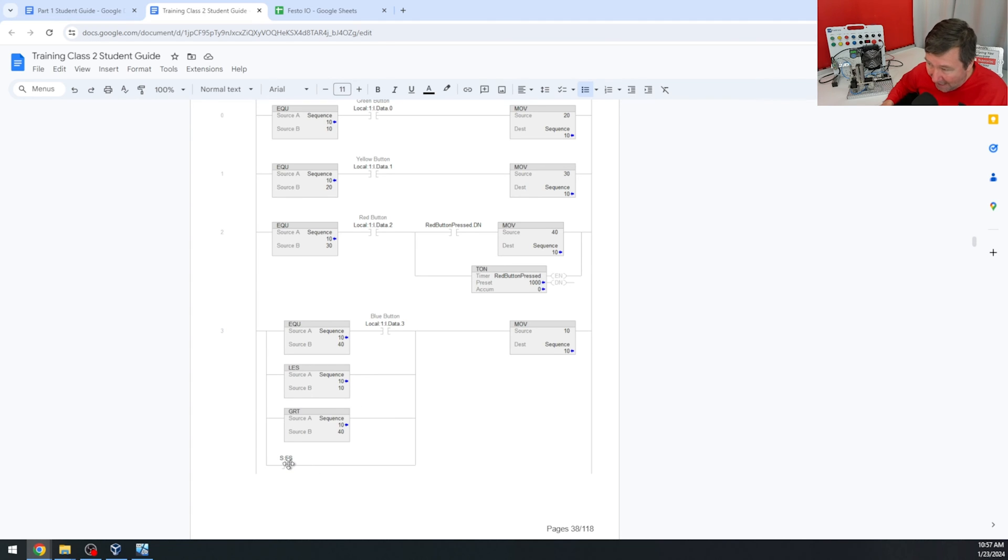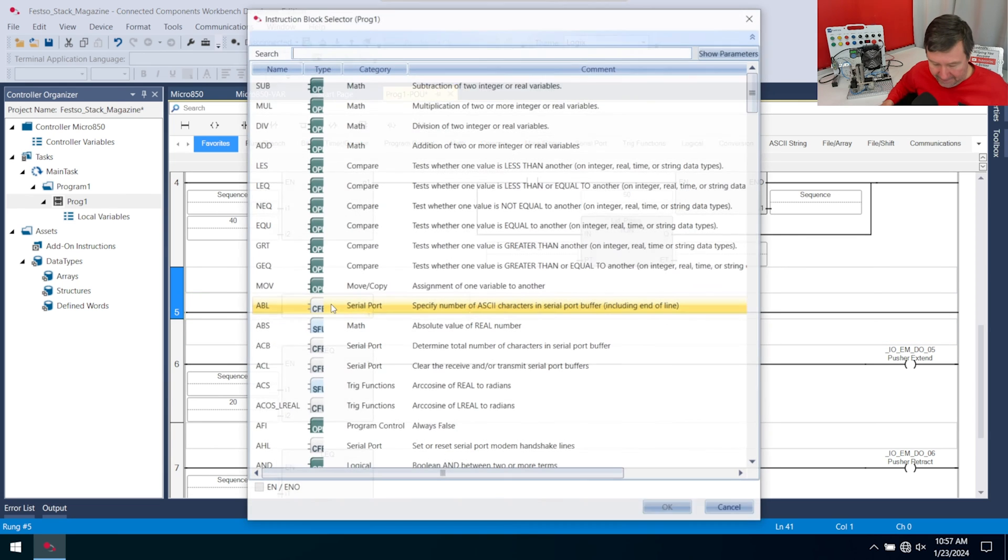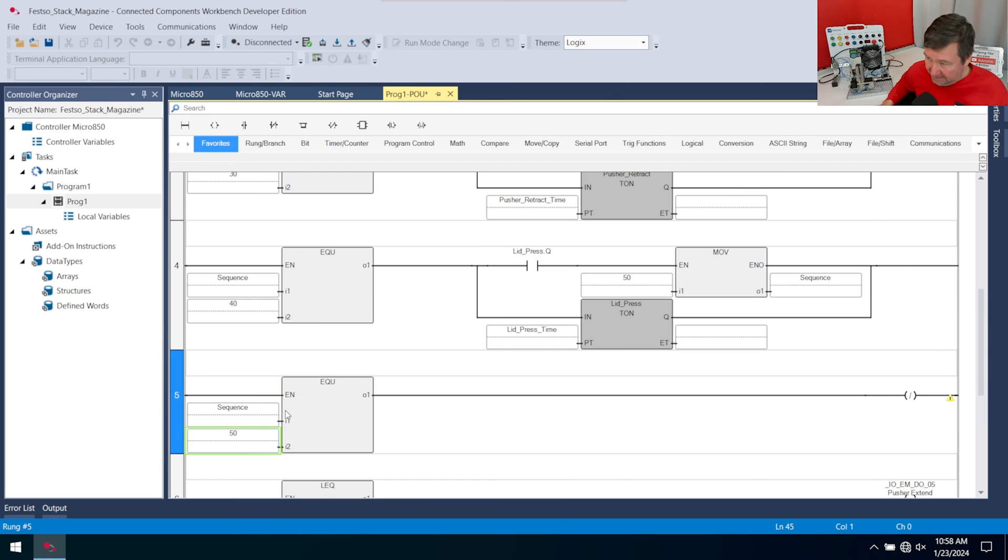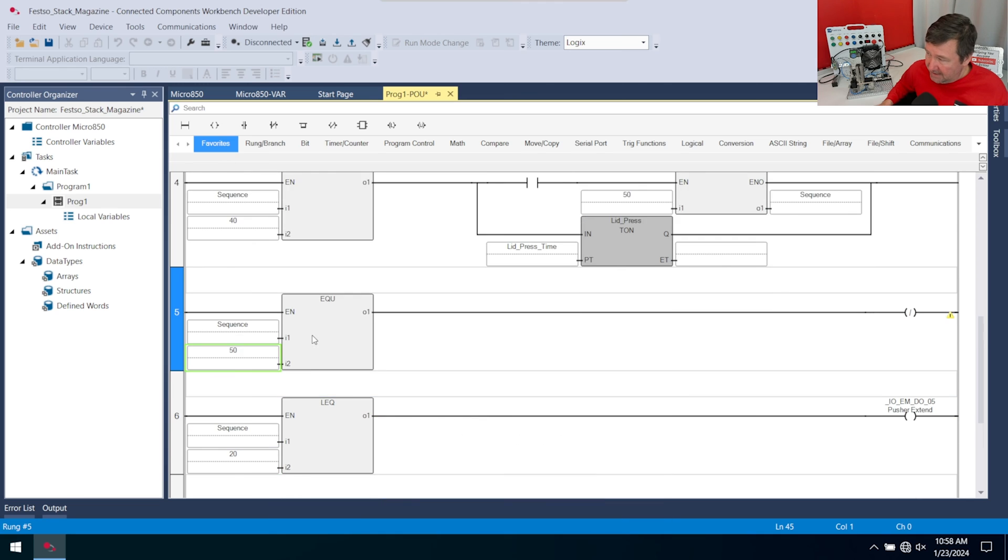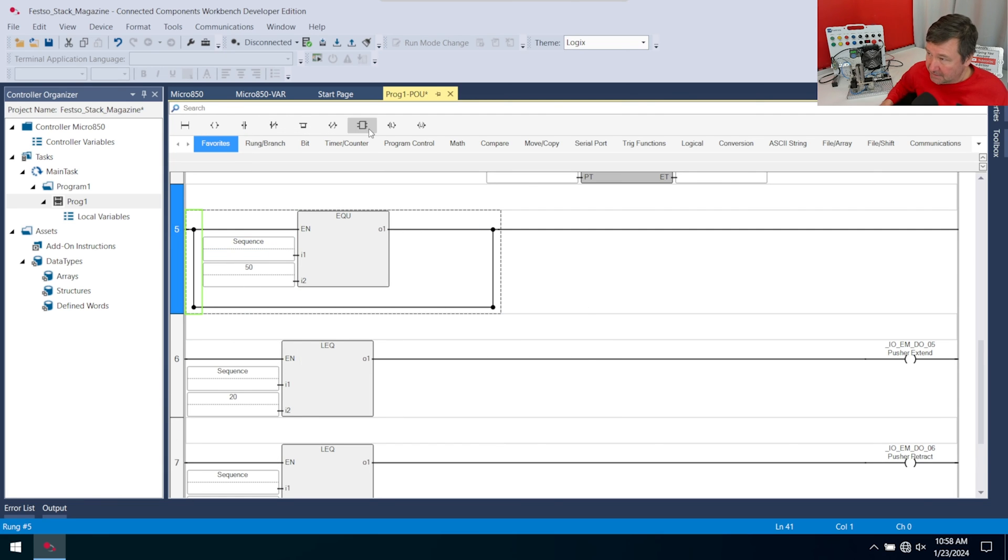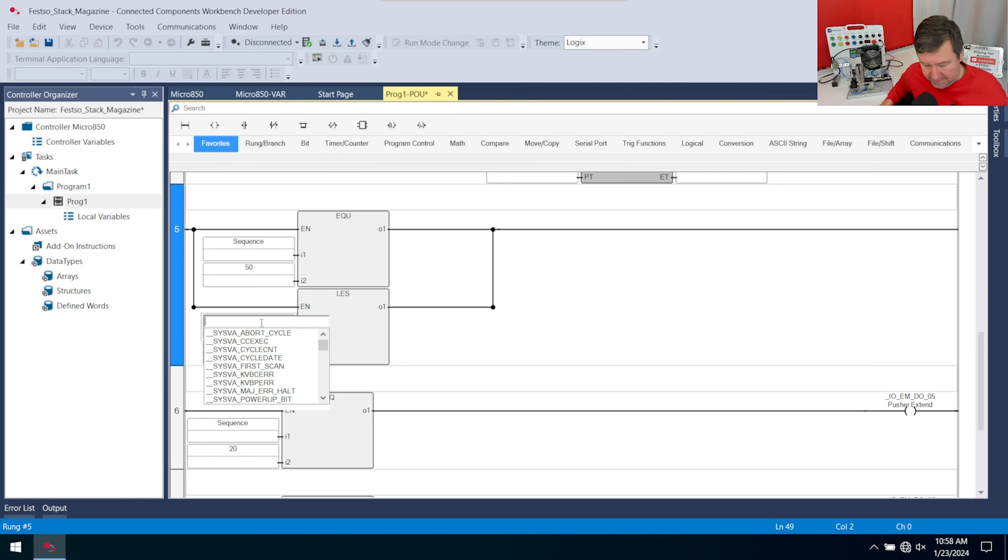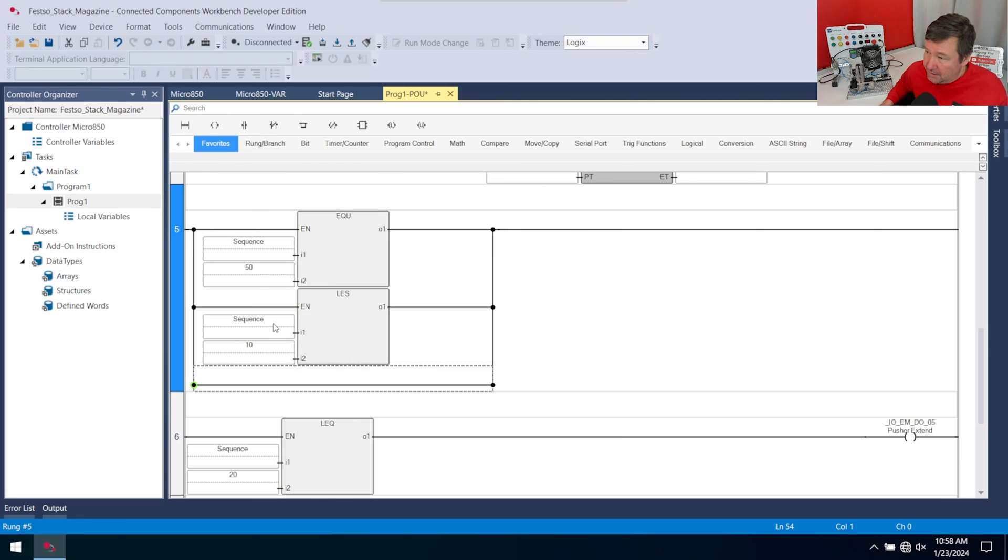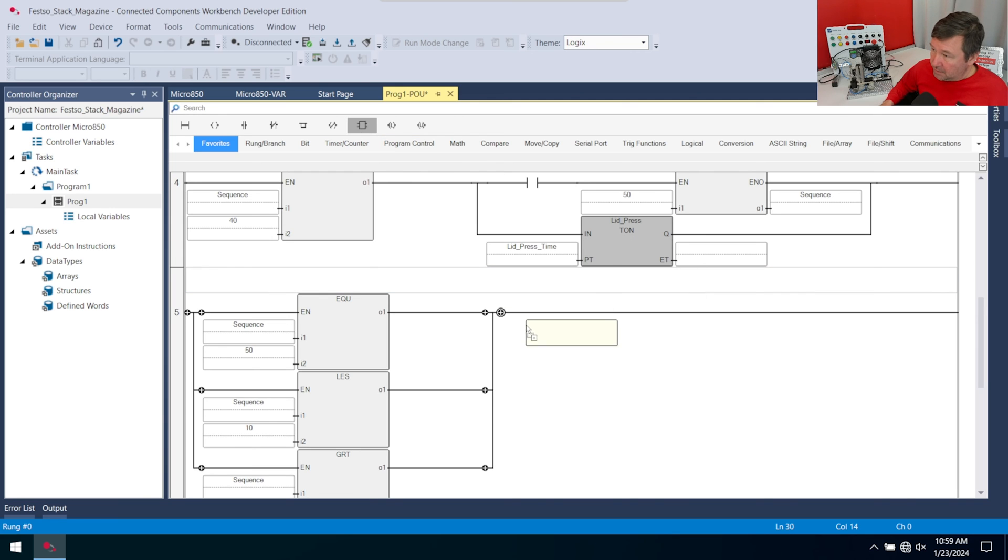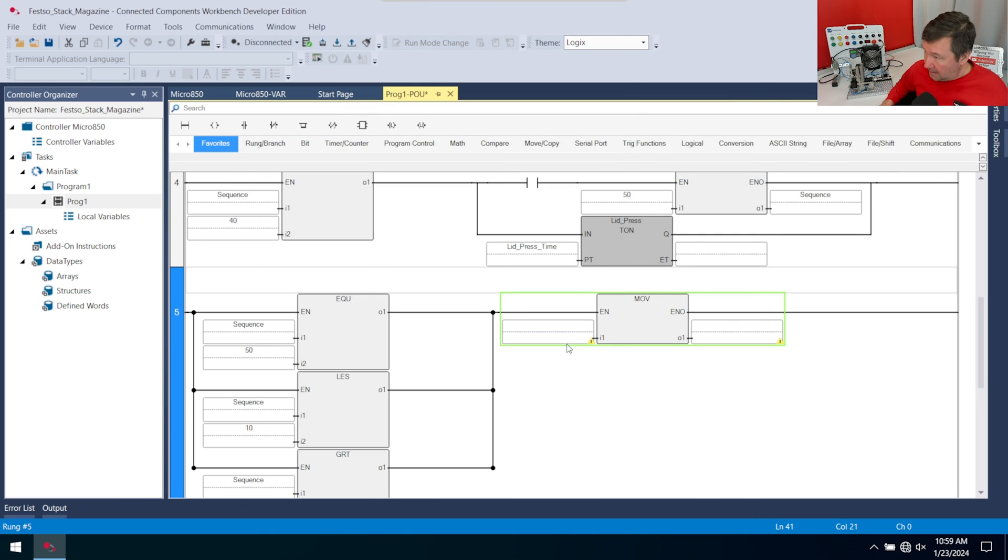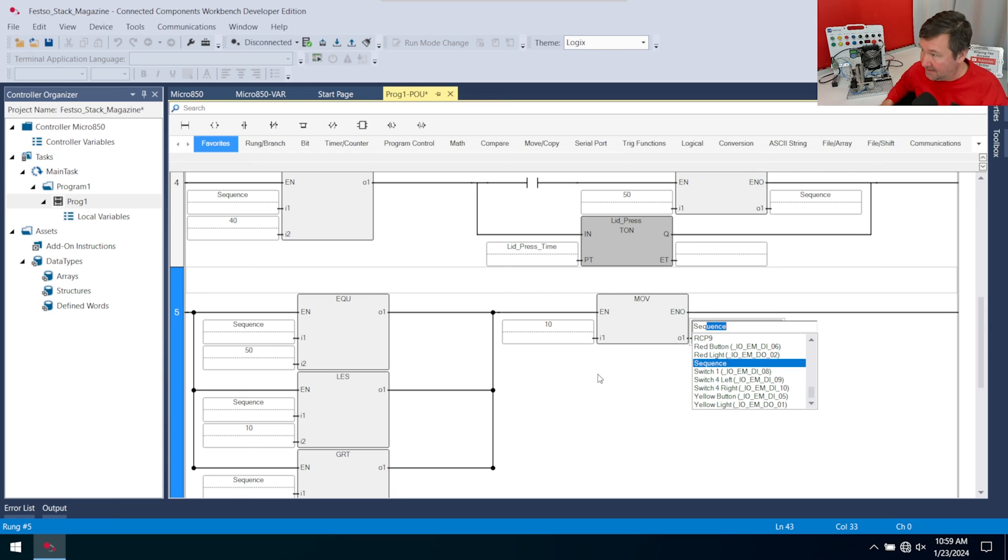In this case we are going to hit this, and this will be an equals. We are going to look at our sequence that it's equal to 50. We don't have the blue button, we're going to leave that as it is. We're going to bring a branch down though because we also have the less than condition. This will be an LES, and if our sequence is less than 10. Let's add one more branch here, and this one will put an instruction block in that if it's greater than 50. In all of these cases we're going to bring an instruction block and put an MOV in, and we're going to move a value of 10, which is our step one of the sequence, back to sequence.